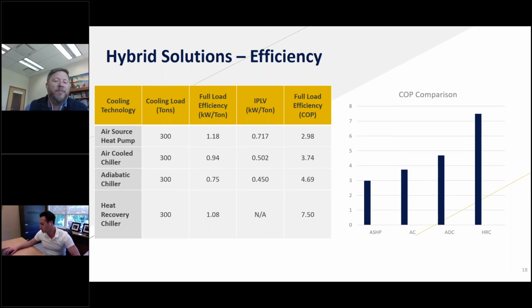So you really have the ability to now drive, if lots of buildings end up being cooling dominant, so we've got this excess cooling load that's more above and beyond what the heating load is. Well, rather than having the entire system be an air source heat pump, we break that up and divide and conquer, and give a more efficient system for cooling only, let that do its work, and then have the air source heat pump there to handle the simultaneous and/or the heating dominant load.